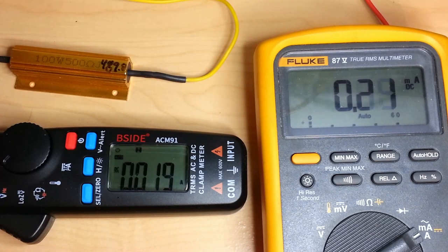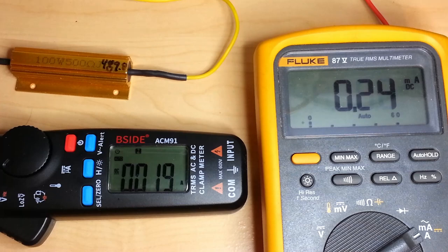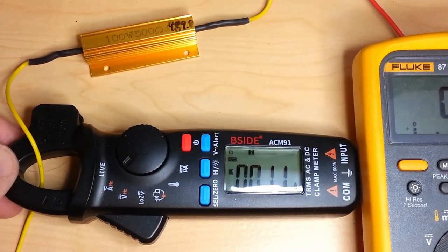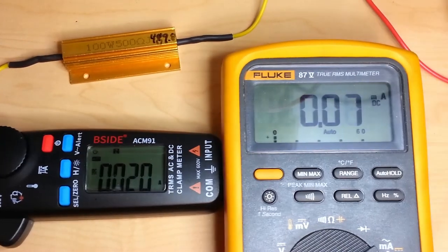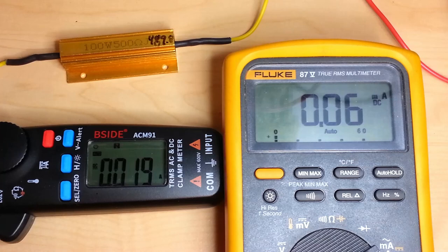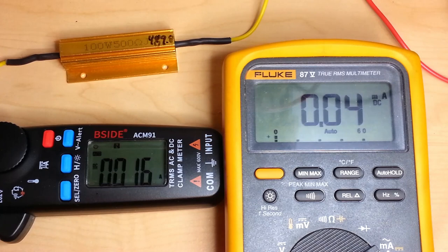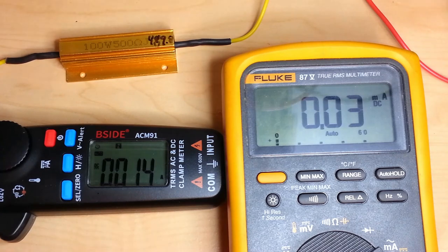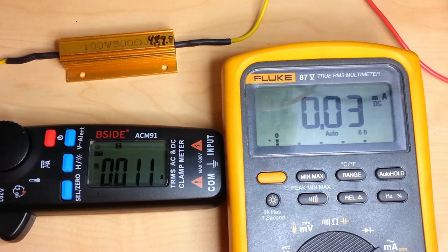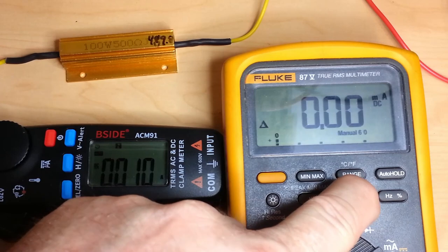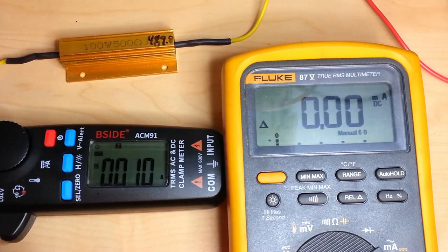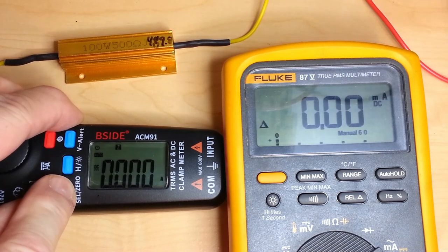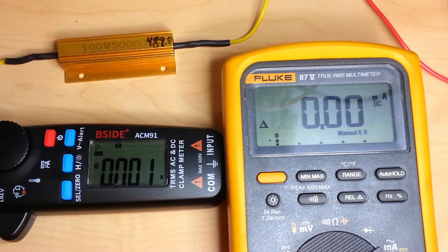I am back in a controlled indoor environment and I'm going to compare the readings on the B-side current clamp meter. I have a 500 ohm, 100 watt resistor going through the clamp, and I have in series with it a Fluke 87 set to the milliamp range, so it's indicating down to one hundredth of a milliamp. That's powered by my HP E3612 power supply so I can control and vary the power. First thing I'm going to do is delta out my zero on both meters.